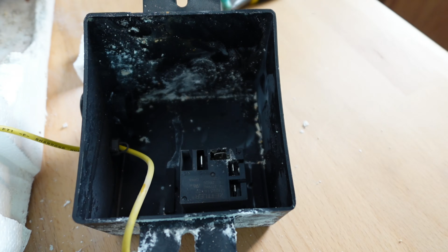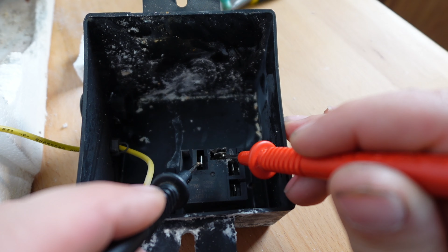Let's turn off the water heater entirely and throw the breaker off for the water heater, so there is no power going to this bad boy at all. Then disconnect the relay entirely from the system—it should have 4 wires going to it. Disconnect all of them. Then with the relay just sitting there minding its own business, check for continuity across this pin and this pin. You're hoping at this moment that there is no continuity.